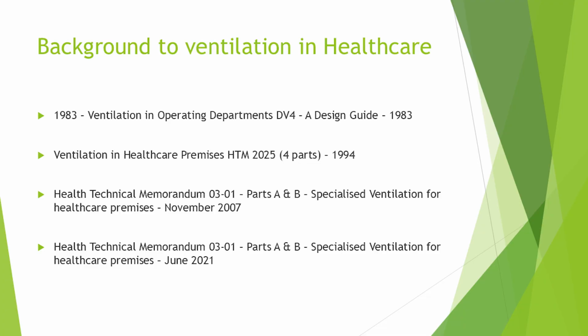Then we moved on to HTM 2025. There are still hospitals today, I'm sure you'll be aware, running ventilation that is built to that standard, 2025. HTM, Health Technical Memorandum 03-01, Part A and B, that came out in November 2007. And that's the one that most people's ventilation, that standard is that they're compliant to.